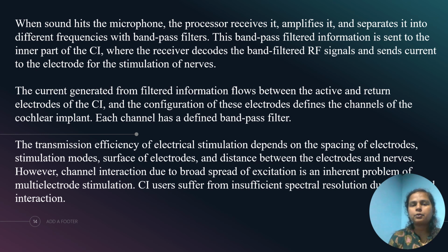When sound hits the microphone, the processor receives it, amplifies it, and separates it into different frequencies with band pass filters. This band pass filtered information is sent to the inner part of the cochlear implant, where the receiver decodes the band filtered radio frequency signals and sends current to the electrodes for the stimulation of nerves. The current generated from the filtered information flows between the active and return electrodes of the cochlear implant, and the configuration of these electrodes defines the channels of the cochlear implant. Each channel has a defined bandpass filter.